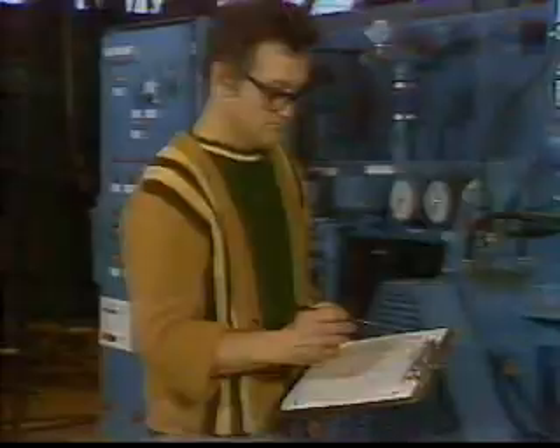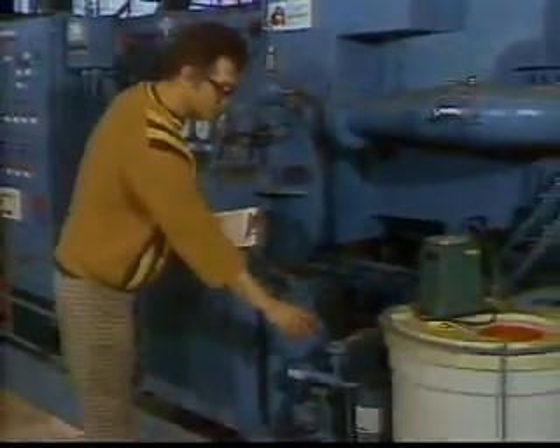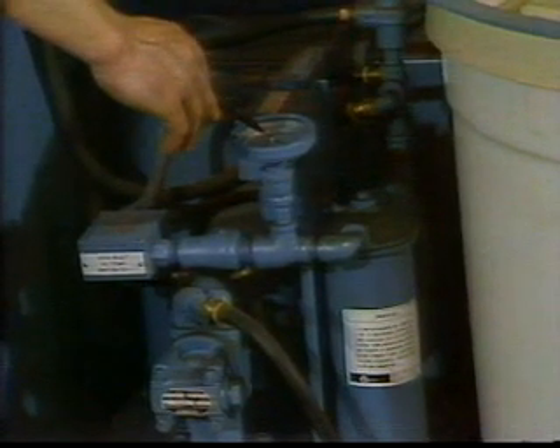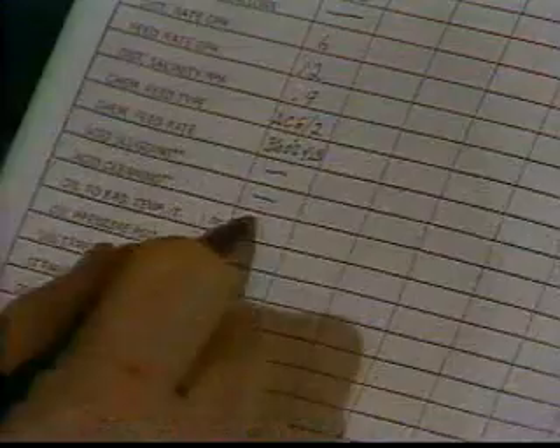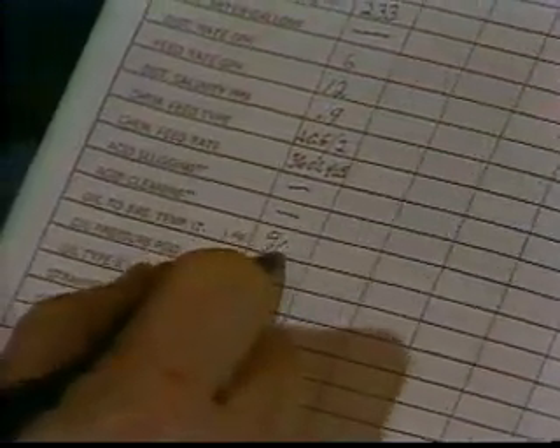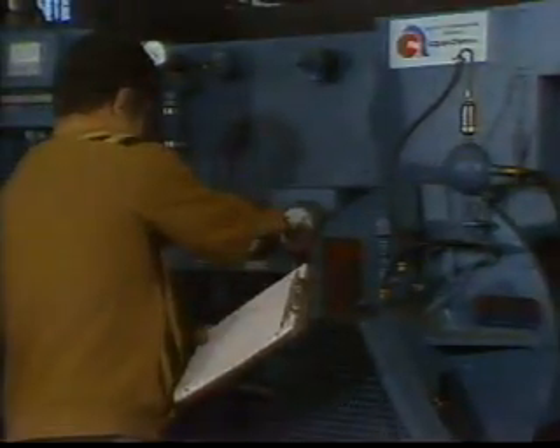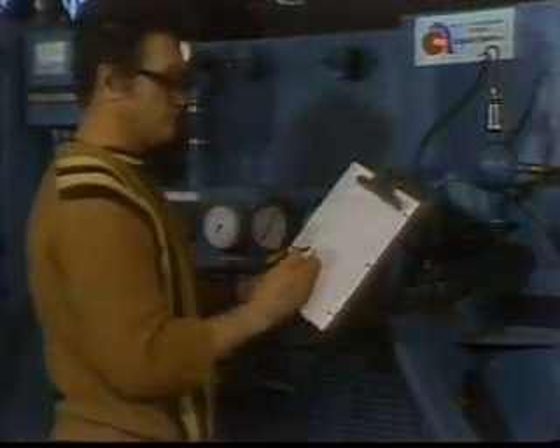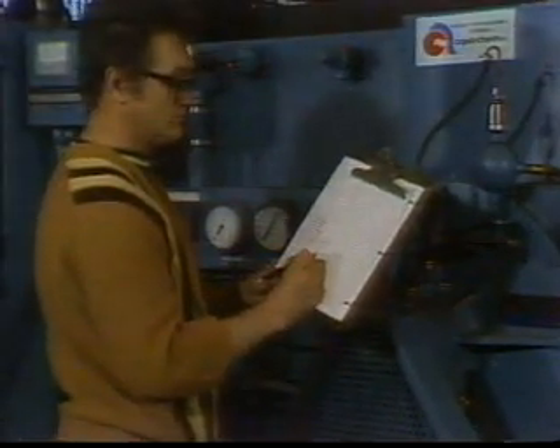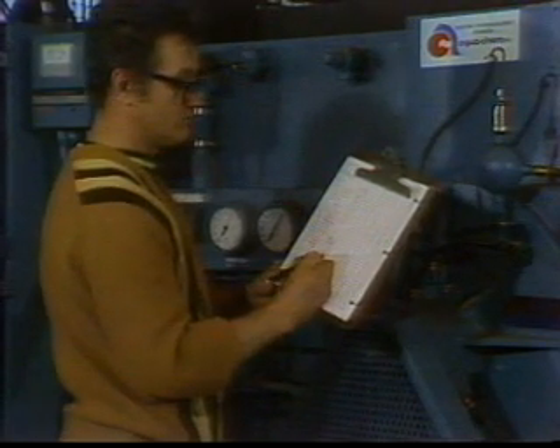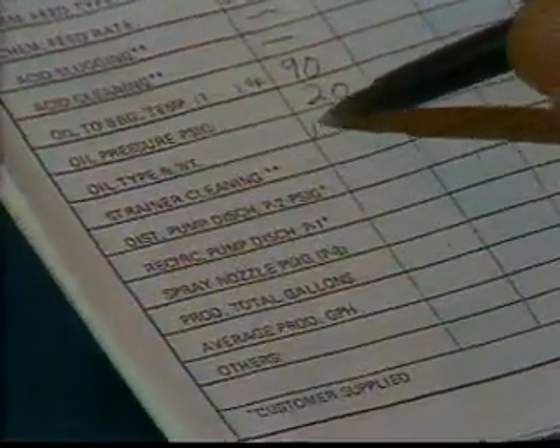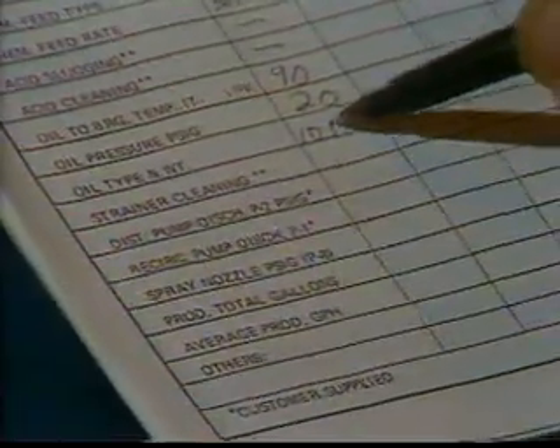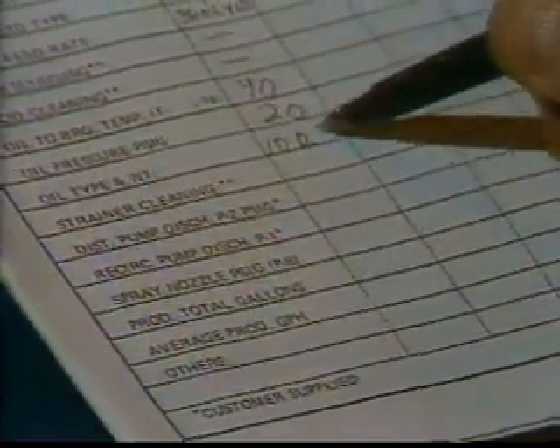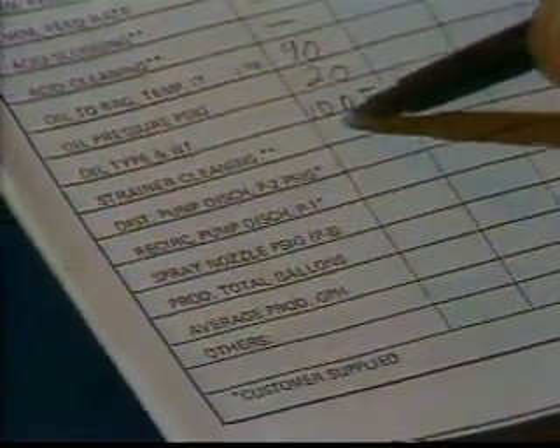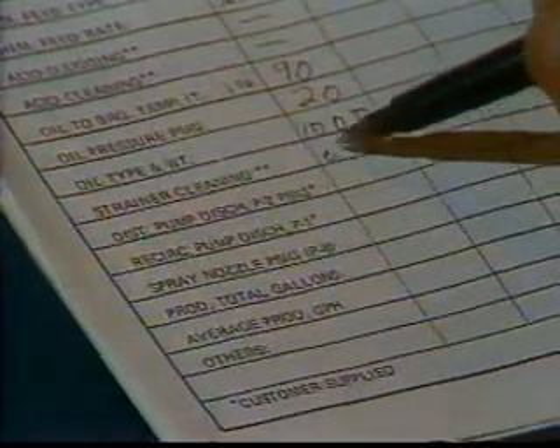Oil temperature for the centrifugal compressor is next and located on the oil pump piping. A temperature of above 170 degrees Fahrenheit indicates a problem with the lube oil cooler. It should be checked for obstructions. Lube oil pressure is the third gauge in this row and logged next. It should be between 15 and 20 pounds per square inch. If it's not, adjust the lube oil bypass valve. Next, log the type and weight of oil that you're using. If the oil filter has been cleaned, indicate this.